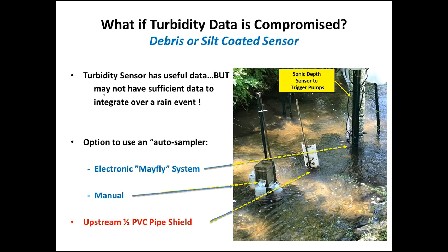Okay, so if you have an obstruction anywhere... As soon as, right, and you'll see this, you'll see algae or something flopping past it, so you'll see a spike, and then it's okay. Whereas as soon as the turbidity increases, the sensor really doesn't detect anything out there because the scattering is in this little hemispherical thing. It's this little ball of material there. So it just sees the light up really close. It's scattered. So that's why the high numbers tend to look better, and the high numbers are what we're interested in anyway. We don't have numbers, unfortunately, that are down in the low range. Marsh Creek is 3 or 4 NTU, but there's no flow, so we don't have that issue.